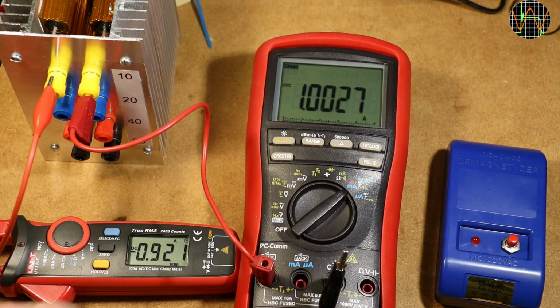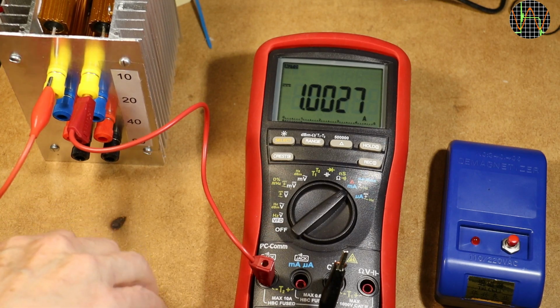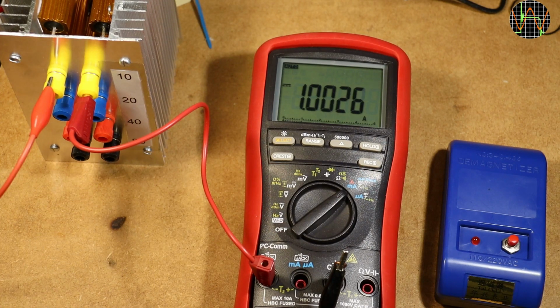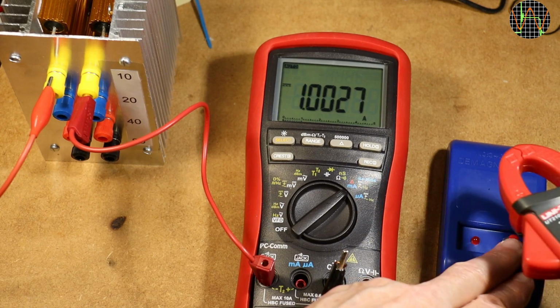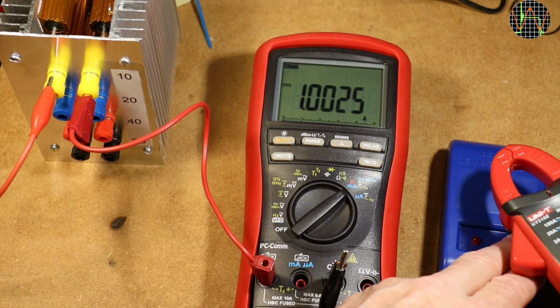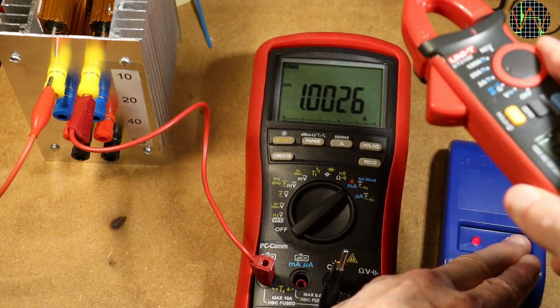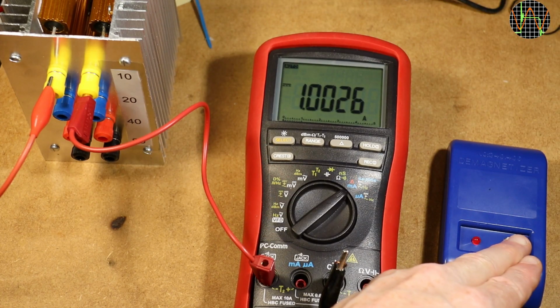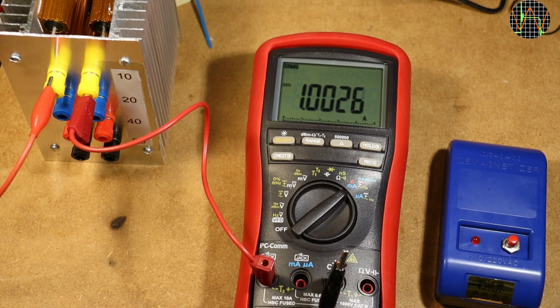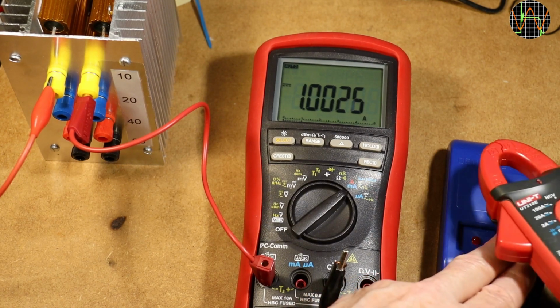The first thing to rule out is residual magnetism of the clamp itself. Hall effect sensors are sensitive to any magnetic fields, and over time the clamp itself can become magnetized from the current carrying wires it measures. So it's good practice to demagnetize, also called degauss the meter regularly.